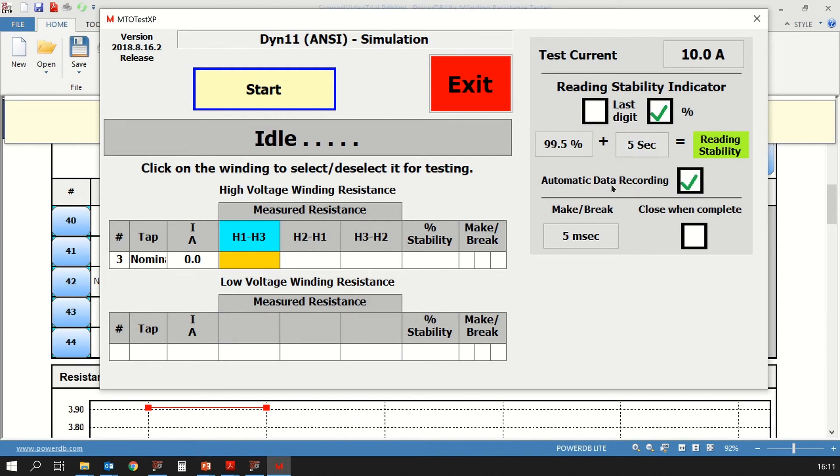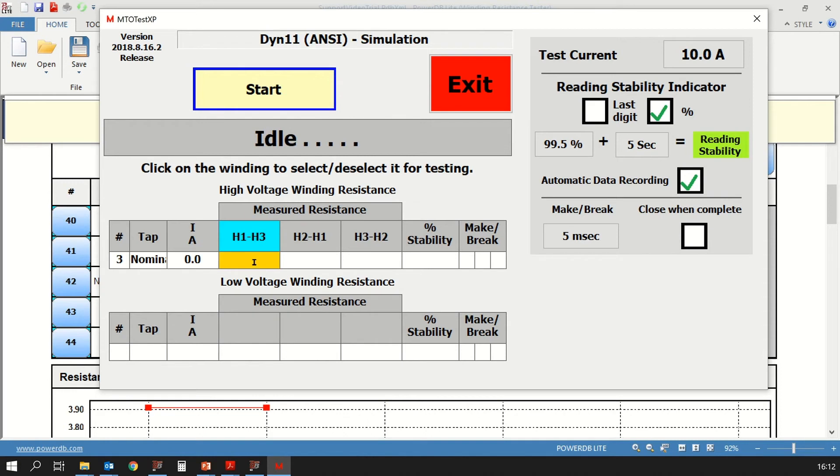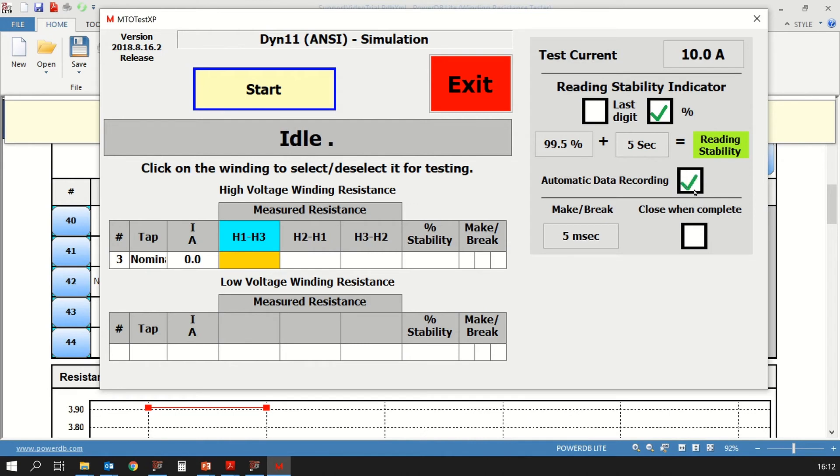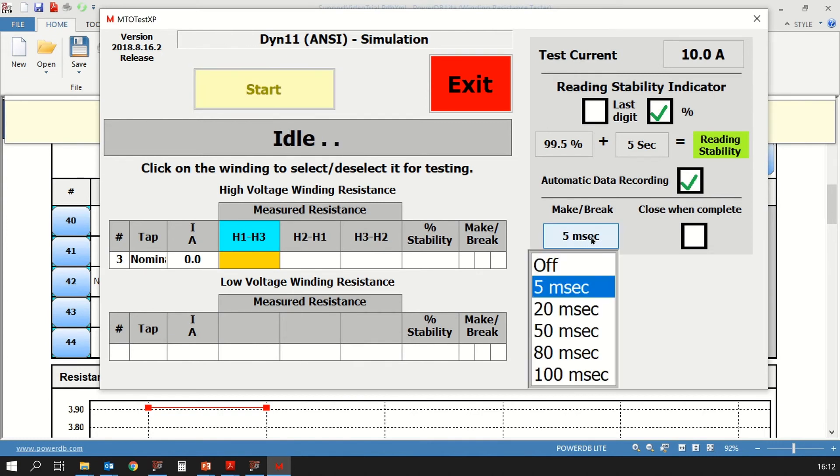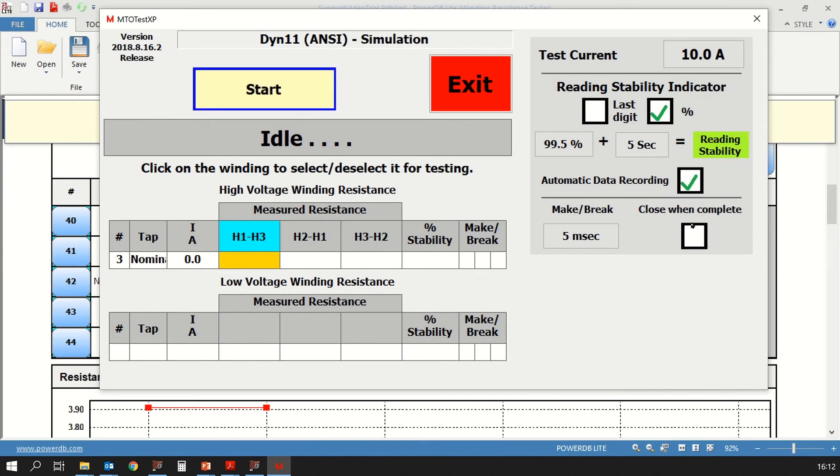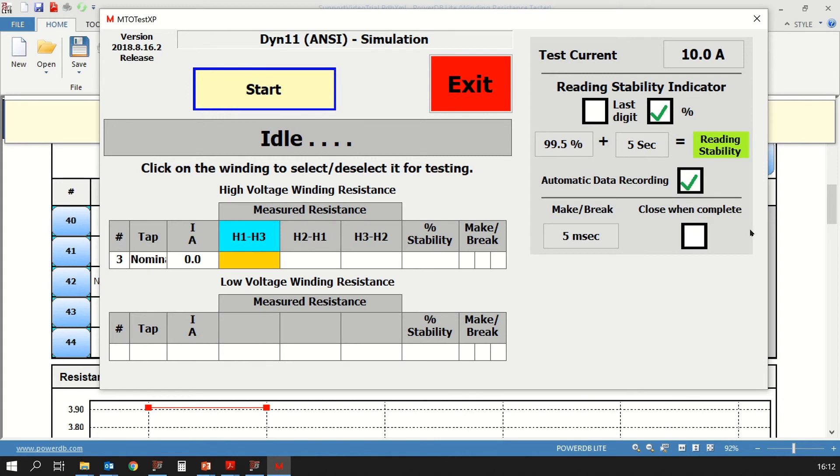Now I have the automatic data recording button so that if it's checked, once the resistances have been measured, they will be automatically transferred to this table. If it's not checked, then after a resistance stabilizes, you would have to click to record the resistance and then the testing can move on to the next phase. I'm going to click it and keep the automatic data recording on. Below that you have the make before break for tap changers, the sensitivity. You can keep it at five milliseconds or that's configurable. You have several other time values that you can select. I'm going to leave that at five milliseconds. If you want this dialog box to close when the testing is complete, you can check this box. I'm not going to check this right now. With all that discussed, I think we are ready to begin initiating a quick test.